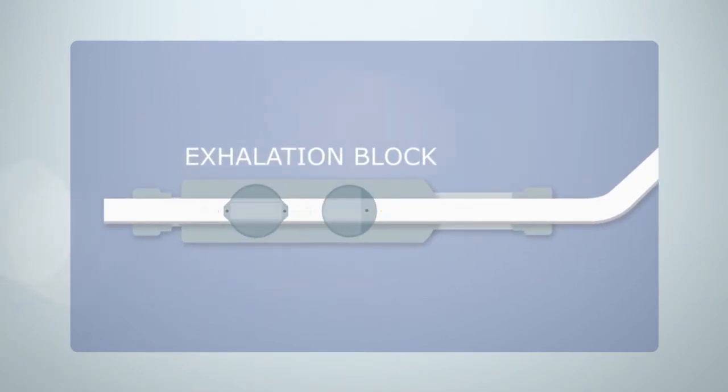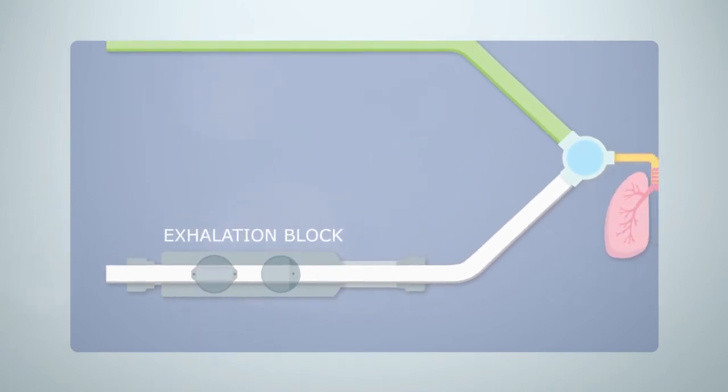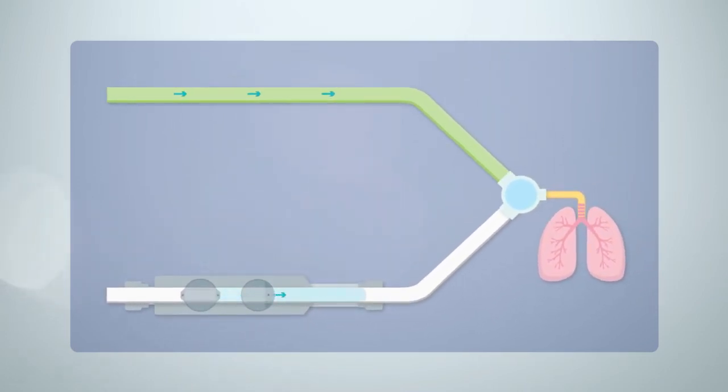When you want the patient to receive a breath, a forward-facing jet gives a controlled pulse of air. This acts as a pneumatic piston adding to the bias flow and diverting gas into the patient's lungs via the Y connector.